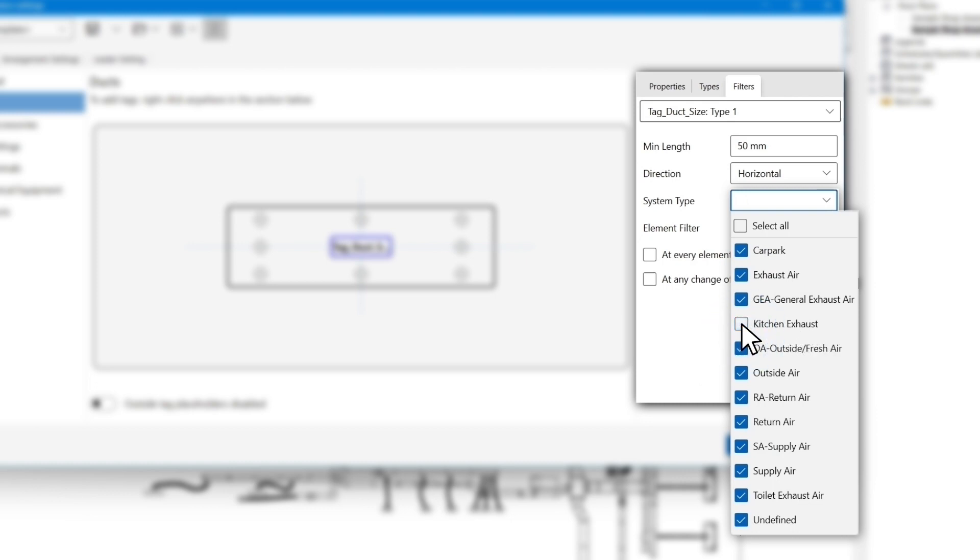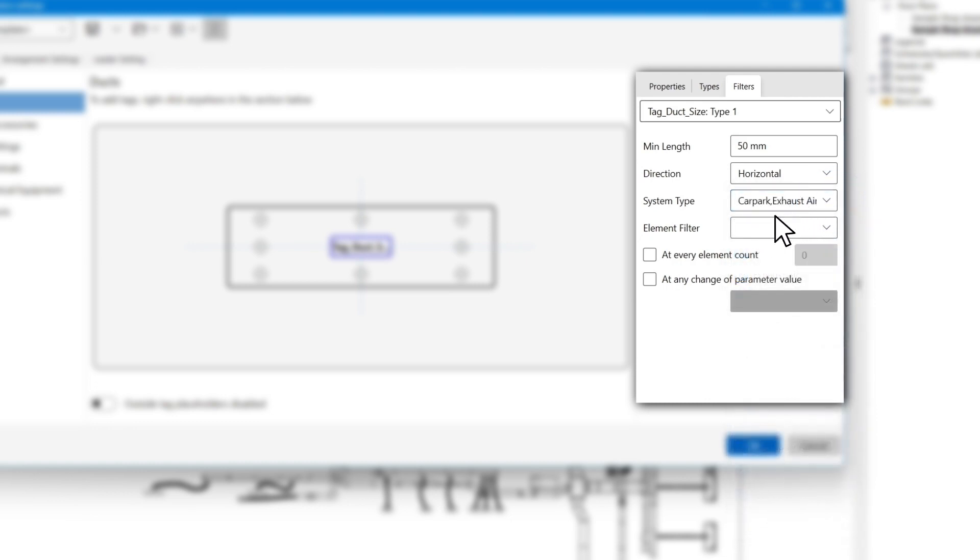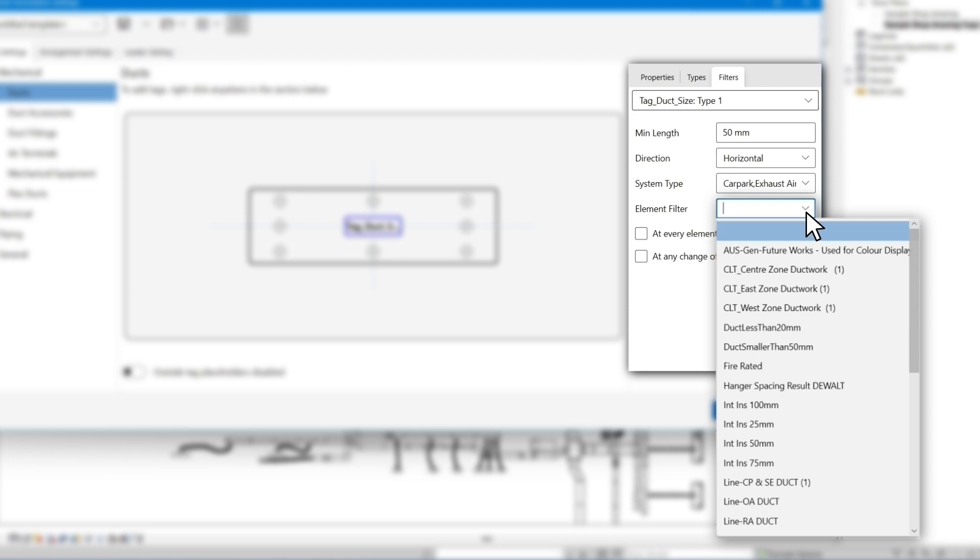We can also filter out elements to be tagged based on their systems. In this video we want the duct size tag to apply on all systems except the kitchen exhaust. So we tick all the systems except the kitchen exhaust systems. You can also read the Revit filters from your model and apply them to the tag settings using the element filter.